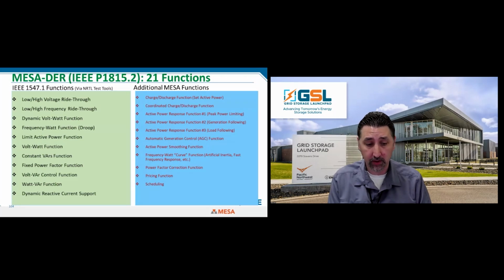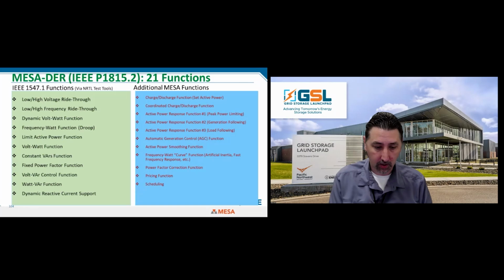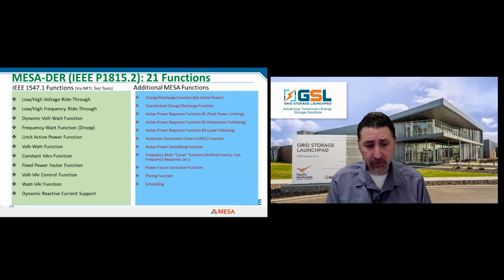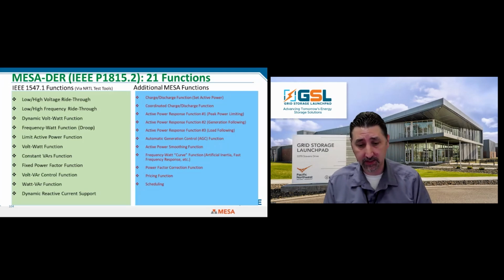It's really important that you think about what 1547 covers: ride through, volt-watt function, continuous VARs, power factor correction - well, it's not power factor correction, it's constant VARs, fixed power factor correction - those exist in 1547, those are what gets tested. But look at all these things on the right side - these are the energy storage capabilities that are not in 1547.